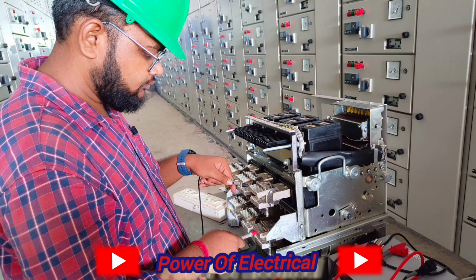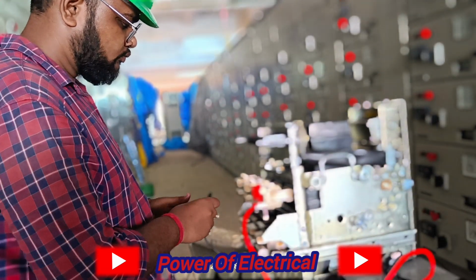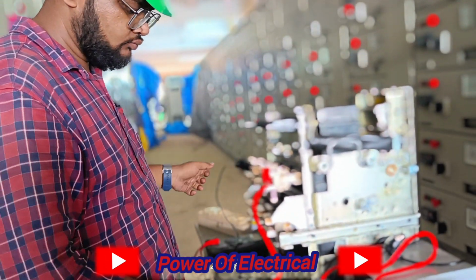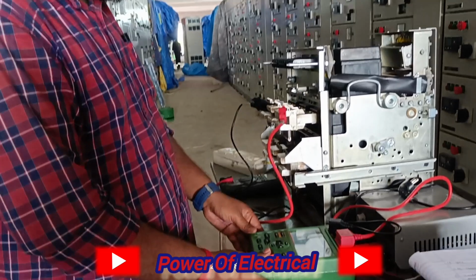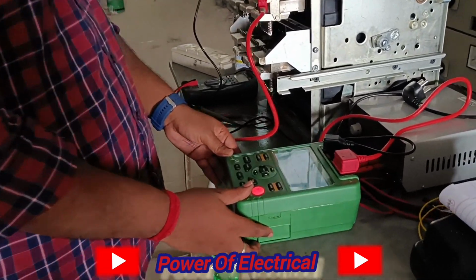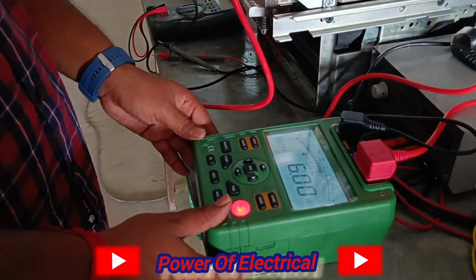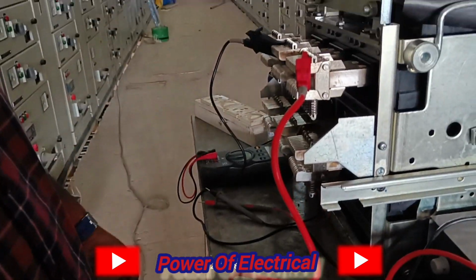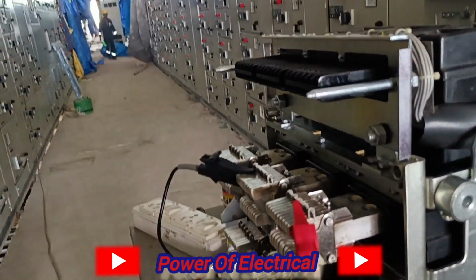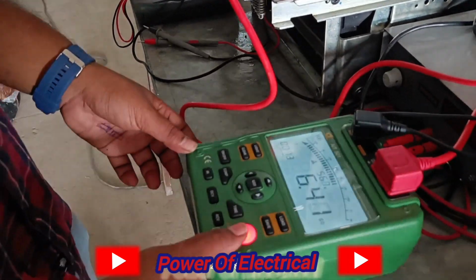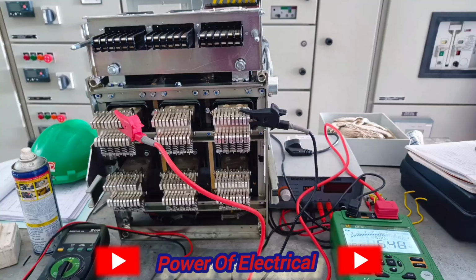After completing pole to pole, meaning off condition, we turn the breaker on and check as well whether the breaker is properly closed or not. Then we check the phase to phase IR testing, and in the same way we apply 500 volt to the circuit breaker, and then we get a value like 6.48 gigaohm. Thus we complete the same sequence: RY, YB and BR.